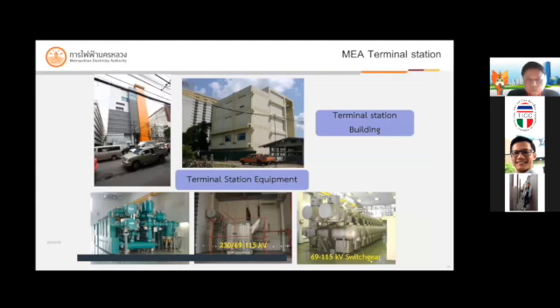This picture shows MEA Terminal Station. MEA Terminal Station is responsible for receiving electricity from EGAT to supply power to substations and customers. It consists of terminal station building and terminal station equipment with 230 kV switchgear and transformer which step down the voltage from 230 kV to 69 or 115 kV, and the last one, 69 and 115 kV switchgear.